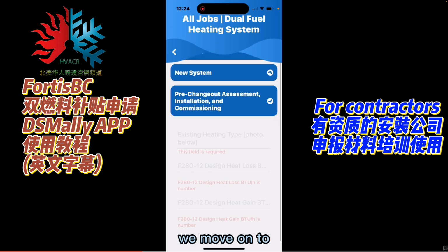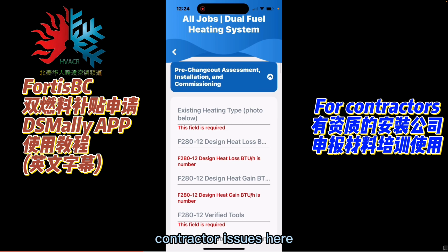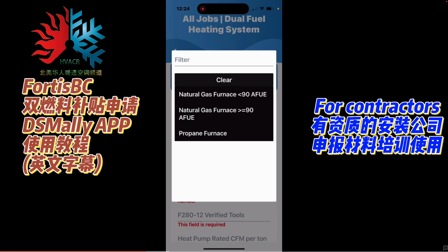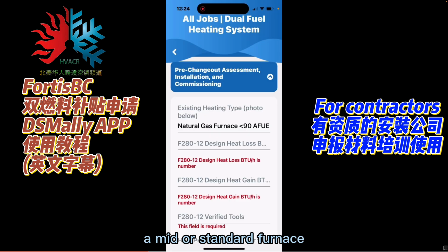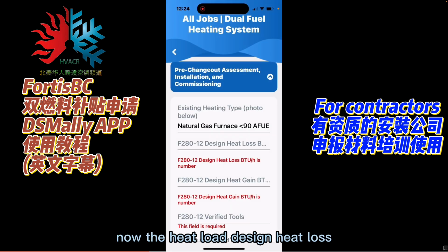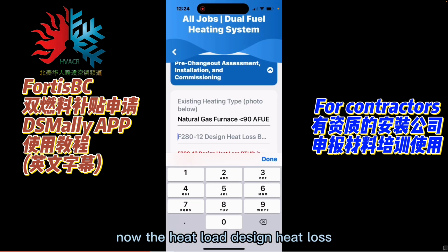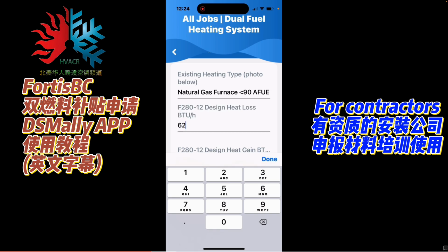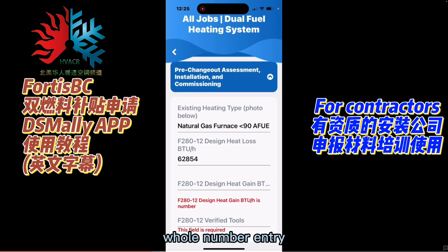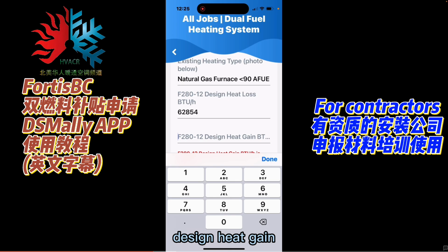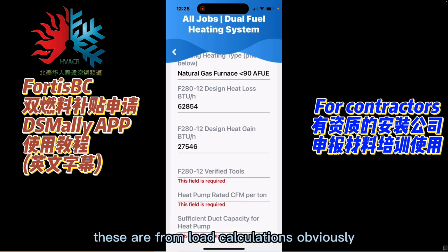We move on to contractor issues here. So the first one is to look up what type of heating equipment you are replacing. I'll select the first of the three, which would be a mid or a standard furnace. Now the heat load, design heat loss, whole number entry, and the heat gain, design heat gain. These are from load calculations, obviously.